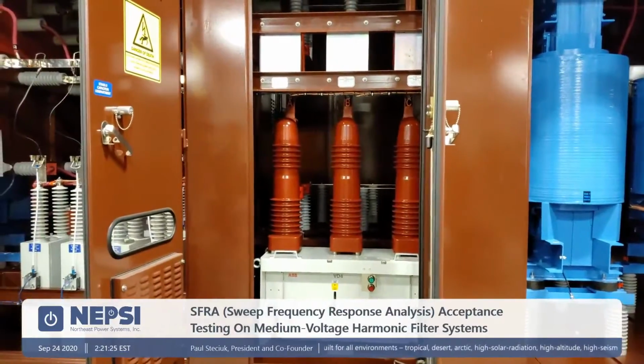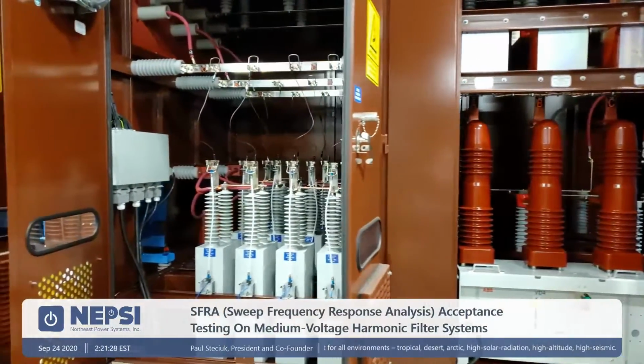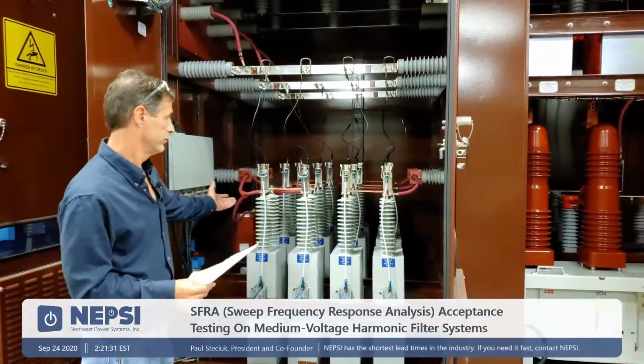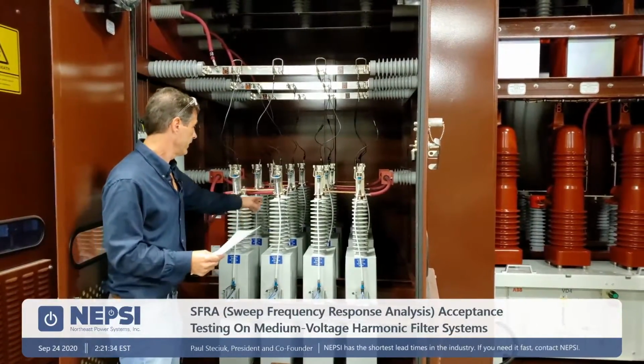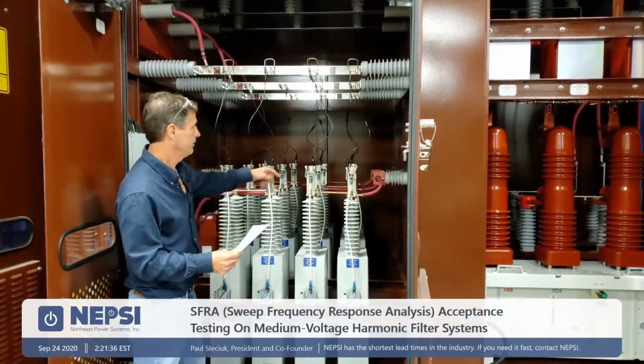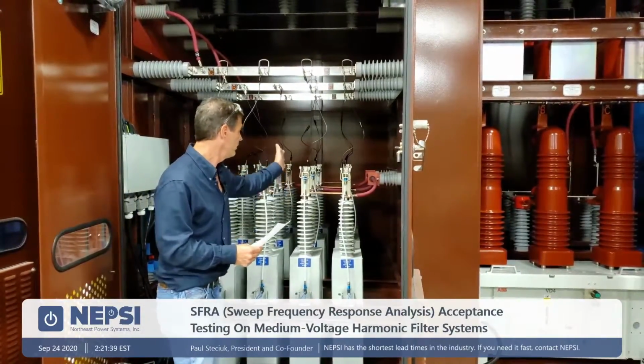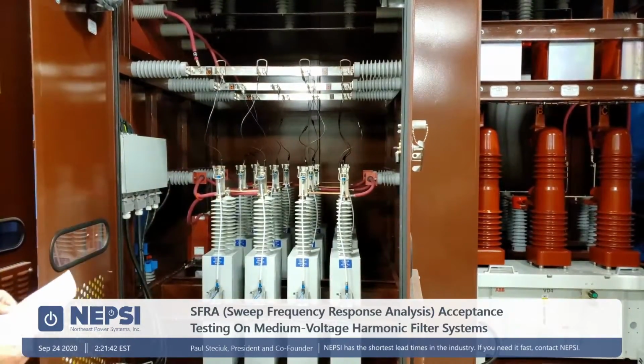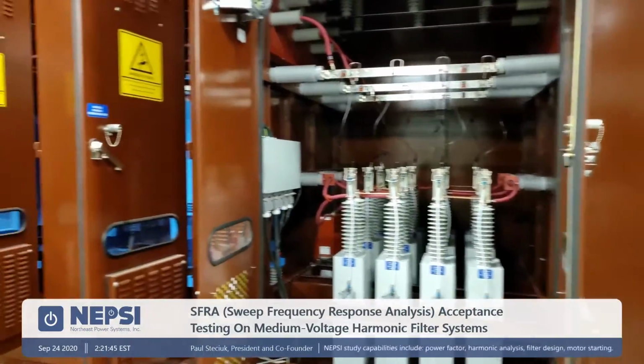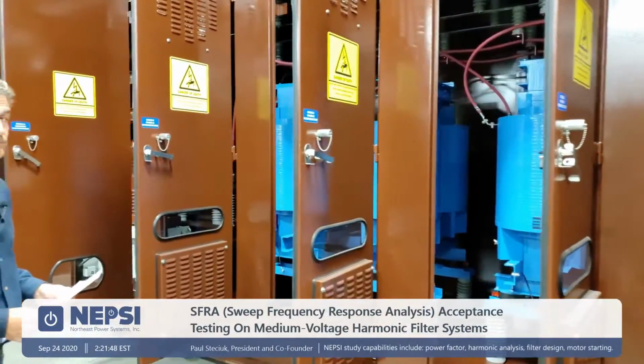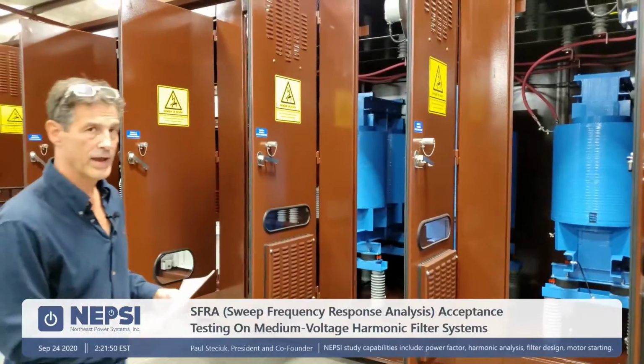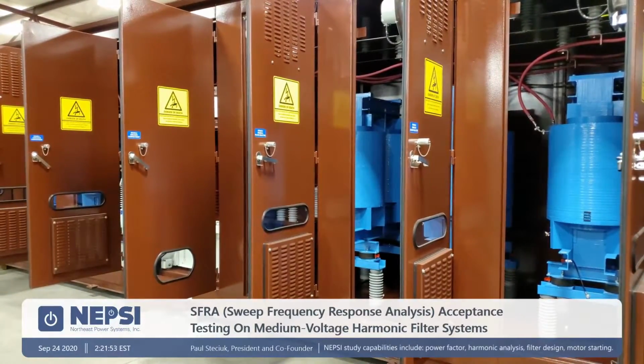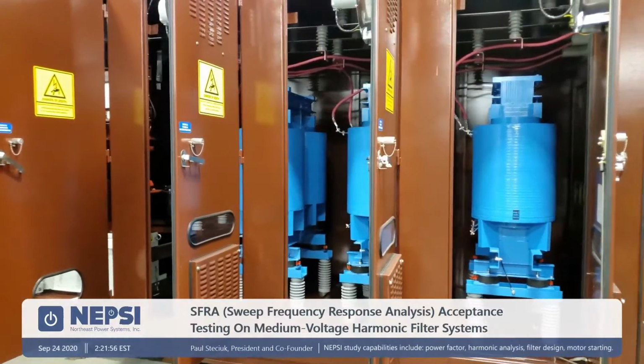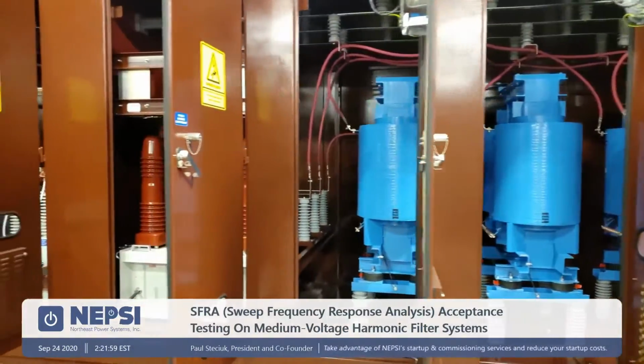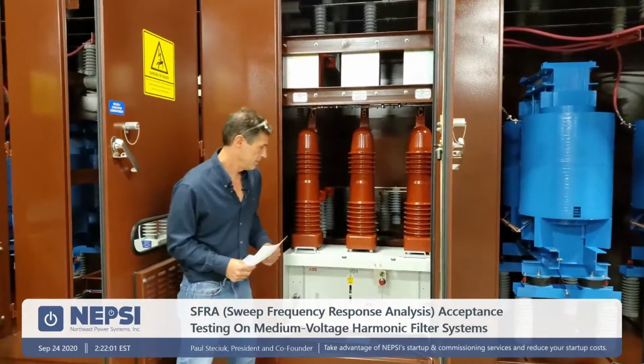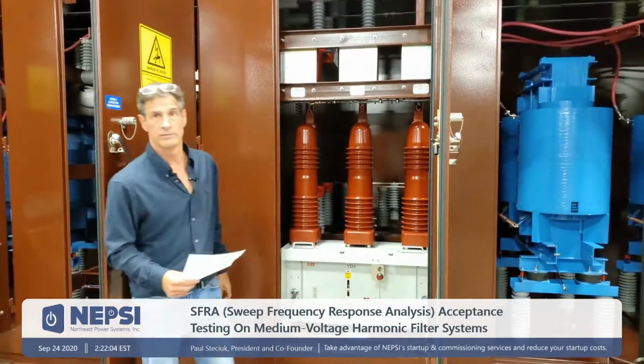And so now we just move down to stage 2. Stage 2 is half the size of stage 3, so there's only 4 caps rather than 8 caps. Again, we have a Y connected and a Y connected with a split Y in between. All the fuses have been connected with a test lead. The stage 2 reactors are a bit smaller because the filter's a bit smaller. And again, this is connected with a breaker, and the breaker is closed.